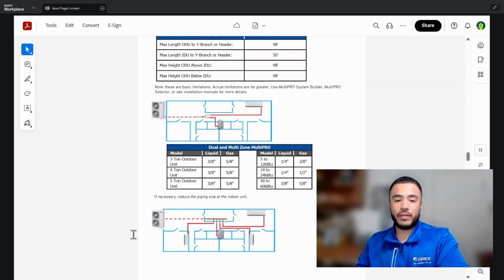Below is an example of a multi-zone with a header installation. It's important to centrally locate this, that way you don't have any really far line set connections coming off of this header. As we see here, they're close to the same sizes, except for this one right here in the middle. But pretty much the basic concept is to centrally locate that header. That way you have reduced piping to do whenever you're out in the field.